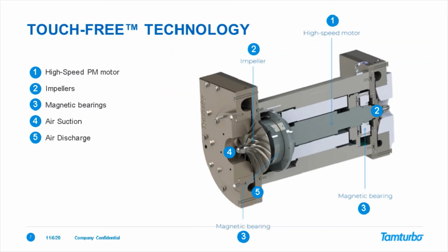And this is actually something that we test for all units, and we have done extensive work on this. And then also in the field, we've had dozens of compressors experience a power outage while the compressor is in operation. What happens is that this motor, which is a permanent magnet motor and it's spinning quite rapidly, turns into a generator. So as soon as the power goes out, the motor starts to generate electricity, which is then fed to the active magnetic bearings, so that we always keep the levitation. So we always keep the rotor in the center, even when the network power is off.